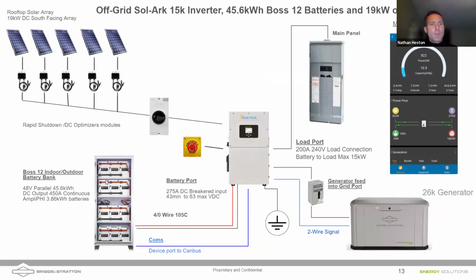Here's another system shown with optimizers. So if shading is an issue, you might go with optimizers, and they give you panel level monitoring. We installed some Tigo optimizers recently, and it's nice to be able to see the production of each of your panels. And if you do have shading issues, these can boost the output of your solar. I'm showing this with a larger cabinet here. These are 12 of our 3.8 kilowatt hour batteries there. Those are 9540 certified in that BOSS 12 enclosure. And we have a heated option for these as well. So if you're installing outdoors in cold environments, that might be a good option.